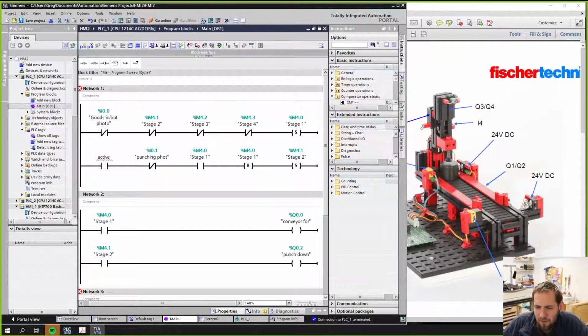If there is a timer involved, you could have a timing stage. As long as the timer's true, we're in the timing stage. And that keeps you then from having to keep that timer latched, as long as you keep your stages set up right, because oftentimes you'd latch the timer with this bottom limit switch. So as soon as we move up, that timer would forget. If you have that set up wrong and you don't have your code right, as soon as we move up, we forget the timer. It goes, whoa, whoa, whoa, back up. And now it has to move that down again. And all sorts of crazy things are going to happen.